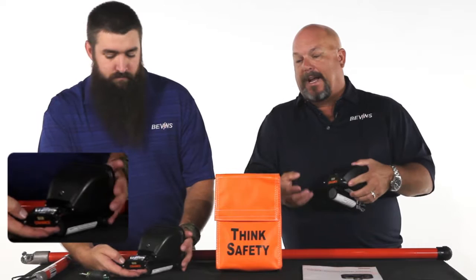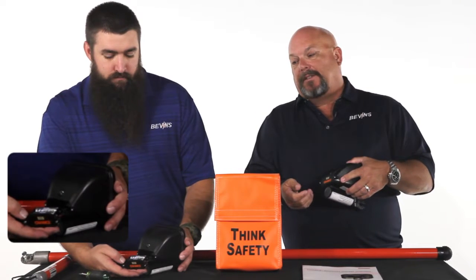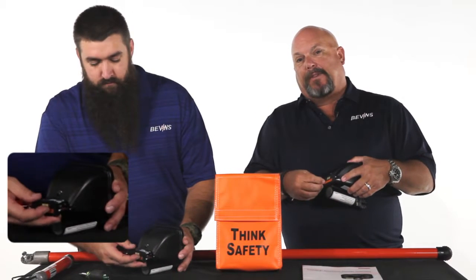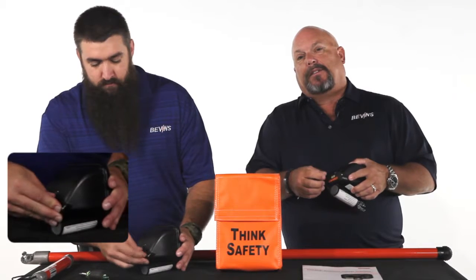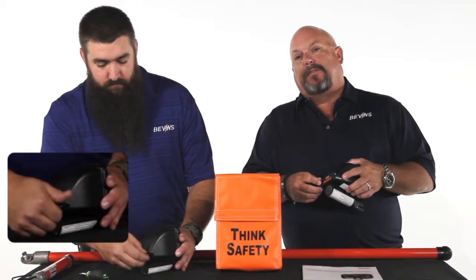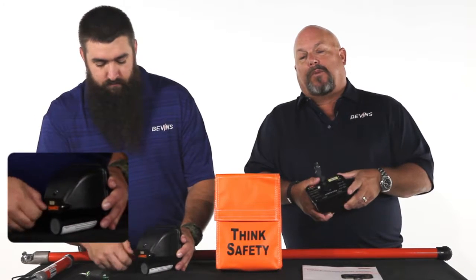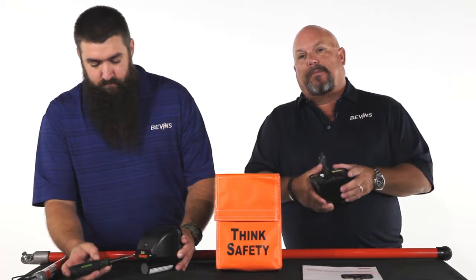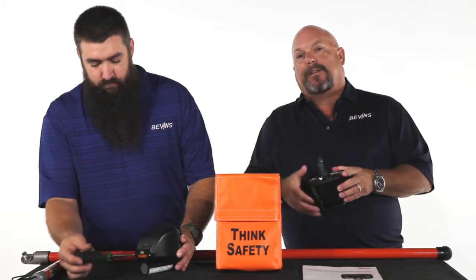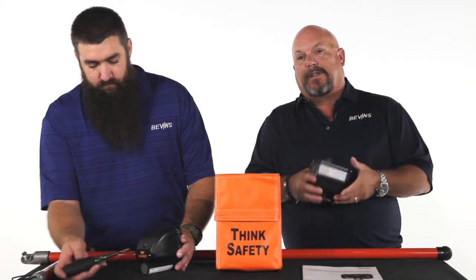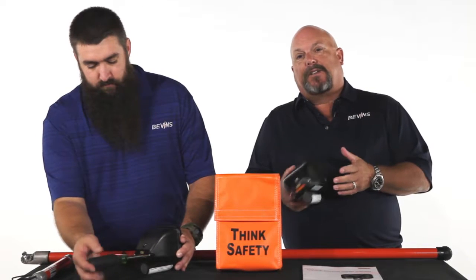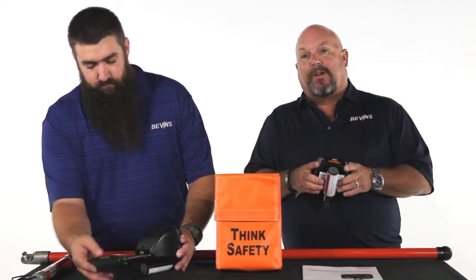So when you pull it out, replace your batteries, put them back in, be very careful not to pinch the wire, tighten the screws back down, and then very important, retest the unit, do the power up, let it go through and come back, make sure that it's operating fully. And if you have a field tester, I would recommend using that as well, or a known voltage.